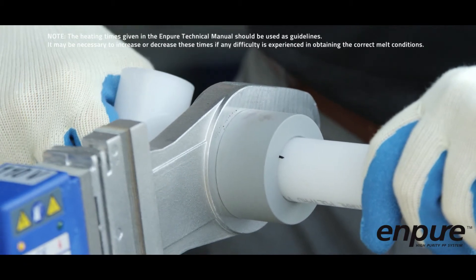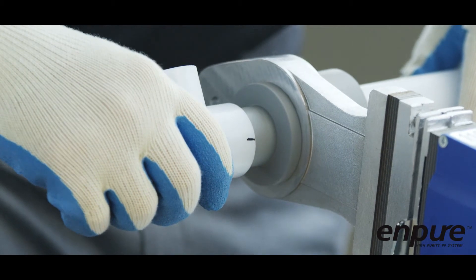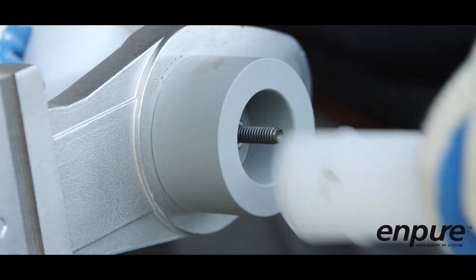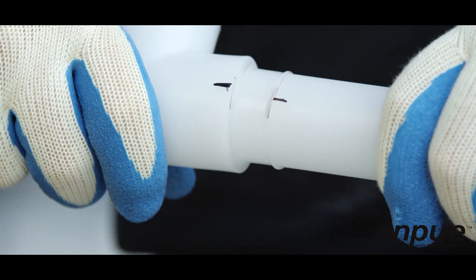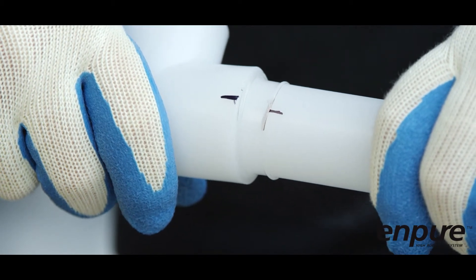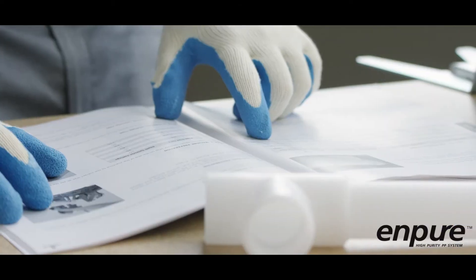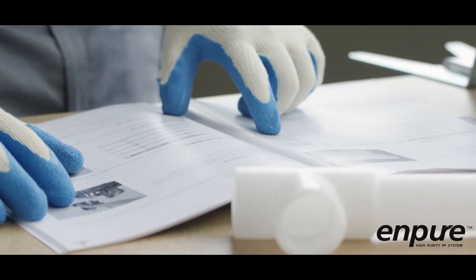While the pipe and fitting are on the heater bushings, a bead should start to form. Once the recommended heating time has elapsed, quickly remove the pipe and fitting from the heater bushings. The heated surfaces should appear glassy, which indicates a proper melt. Immediately fit the pipe into the fitting socket up to the previously marked insertion length. Do not turn the pipe in the fitting socket. This process must be achieved in the welding time given in the table in the Enpure Technical Manual.